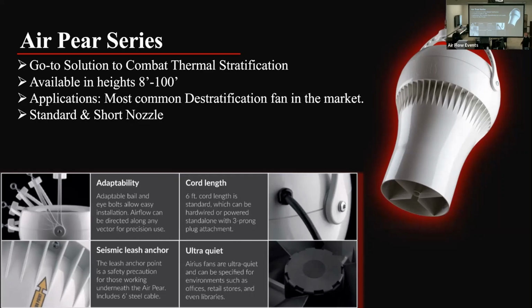The seismic leash is another one I'll highlight. I actually sold a project last week based on just the seismic anchor that we've got right here. The main reason was that a competitor of ours had gone in there and talked to them. They did not have a secondary way of keeping the fan in the ceiling. Their local code required them to have that. So that's another high point too: check the local codes and see if they have to have a secondary way of mounting the fan in the ceiling. The competitor did not have that. They lost out on that because we did. So that's an important point as well.